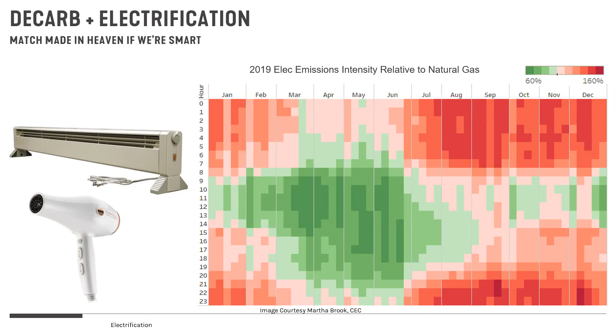Now what happens if you use more efficient equipment? This is that same graph where instead of electric resistance heat, what if we used a heat pump? We'll talk all about heat pumps next week, but the thing to remember today is that heat pumps tend to be around 3 times as efficient as electric resistance heat. So they have a coefficient of performance of around 3, sometimes as high as 5, sometimes as low as 1.5, but they tend to cluster around 3.